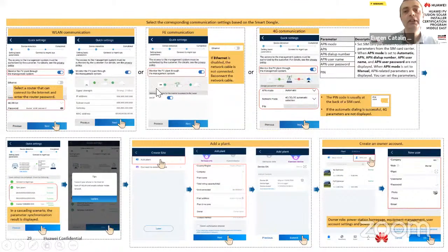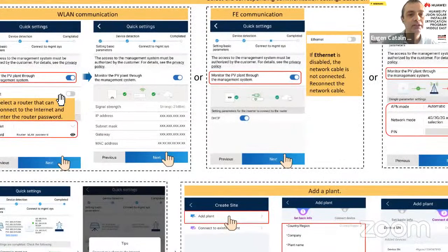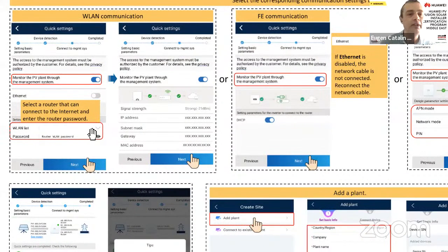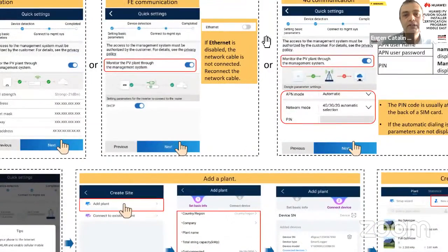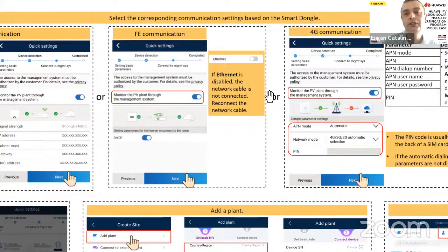And we reach the page where we need to connect the inverter to the internet. What will we have on this page? First, if I use a WLAN FE dongle, or I connect the L1 through built-in WLAN, I will have this page with WLAN connection. I need to choose the local Wi-Fi and the password of the Wi-Fi. And the result will be this, connection to the management system. If I have a WLAN FE dongle and I connect the dongle with an Ethernet cable, I will have this FE Ethernet communication, and DHCP will be enabled on the inverter. It is enabled by default, but it's better to check.